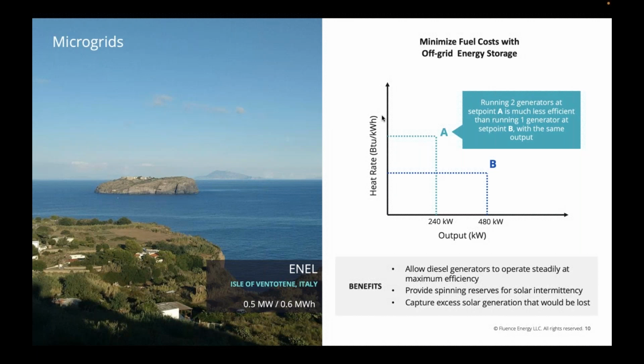One of the interesting things is finding a way to optimize the use of that diesel generator. Instead of running for reliability with 2 generators at minimum load, we know minimum load has a less efficient set point, so you have a higher heat rate, burning more fuel, with higher CO2 and other emissions. If you can run just one at a more efficient set point, you can reduce emissions by running the same amount and use the backup reserve for storage instead.